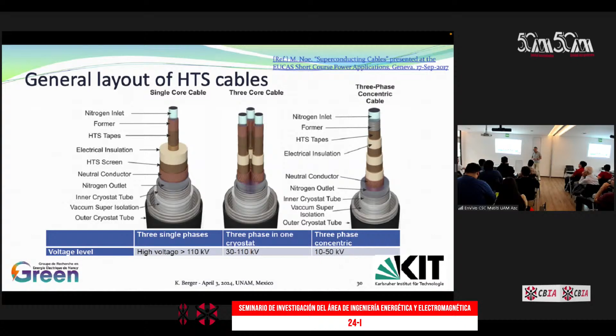In the other case, in the range of 30 to 100 kilovolts, you might split the conductor into three different cables, but all these cables belong to the same cryostat, so they share the same liquid nitrogen and the same cryostat. At the end, if you go to higher voltage, for example higher than 100 kilovolts, you need to split the three-phase cable into three cryostats, three cables, because the thickness needed for the electrical insulation is bigger. So it is more efficient in terms of cooling to split into three different cables.